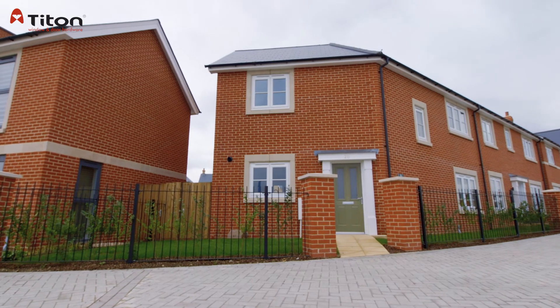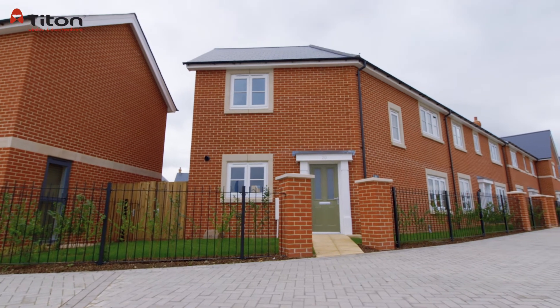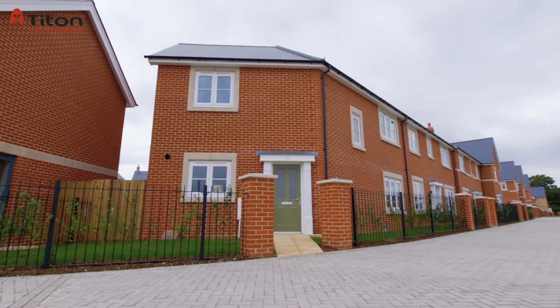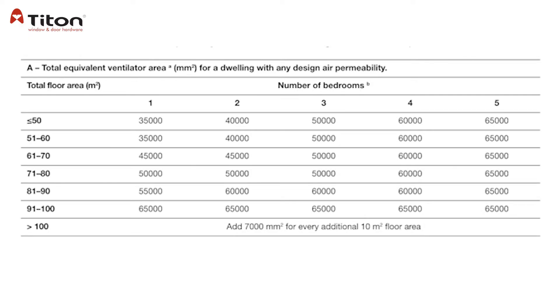This property requires a total of 60,000 millimetres squared EA because it is 90 metres squared in floor area and has three bedrooms. Let's begin our check to see if there are enough vents to give us the 60,000 millimetres squared EA required.